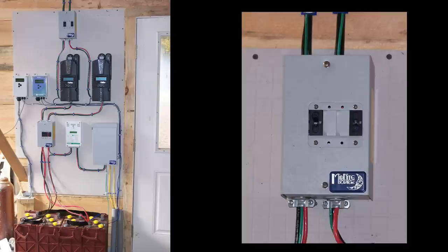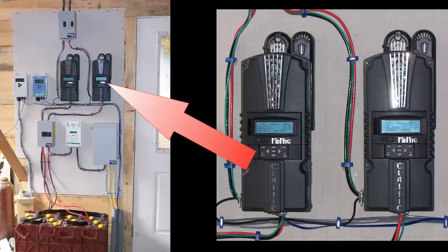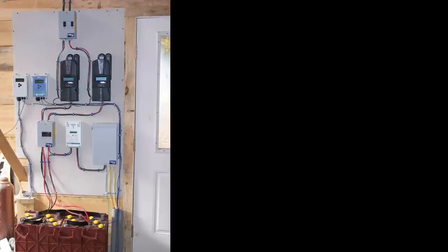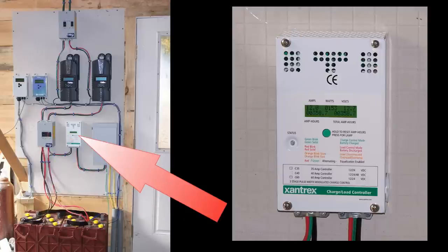The power comes in from two solar panel sets through two 80-amp circuit breakers, which are used as a power disconnect. Each line goes to a MidNite Solar Classic 150 charge controller, where the voltage is stepped down to provide the proper charging voltage and current. From the controller, each power line goes through a 100-amp circuit breaker panel, which is used to disconnect the power from the batteries.